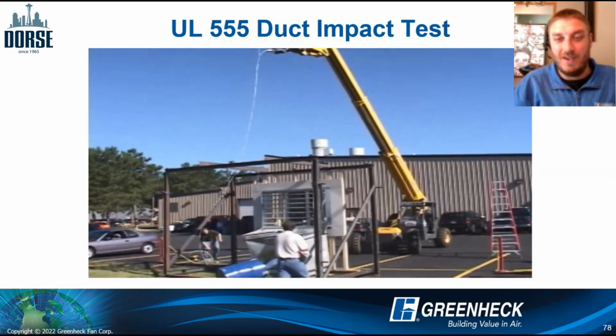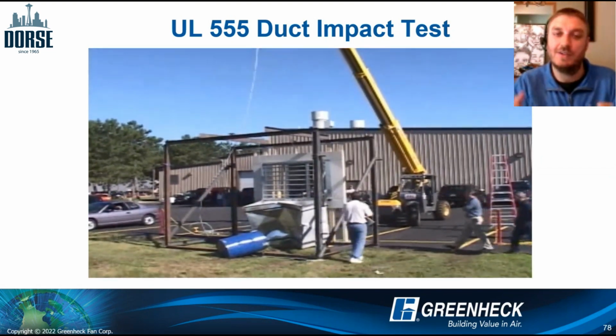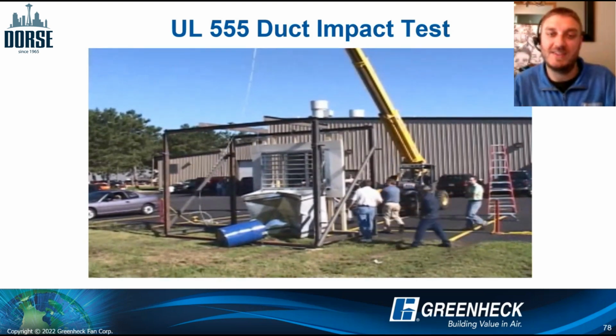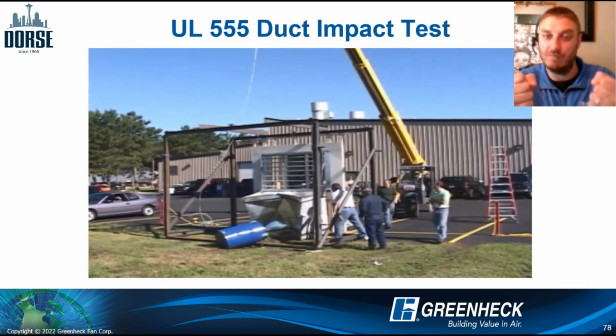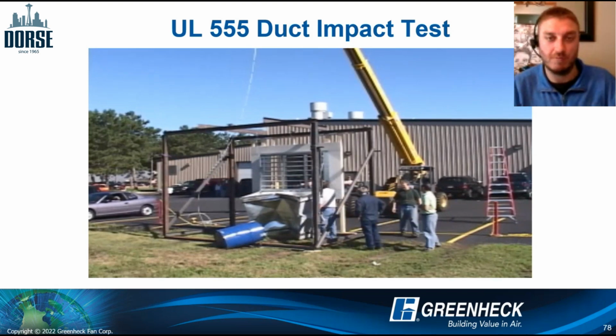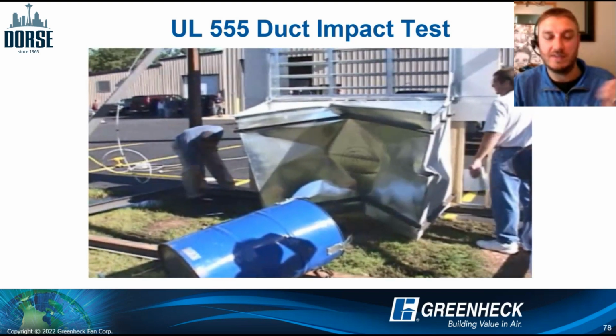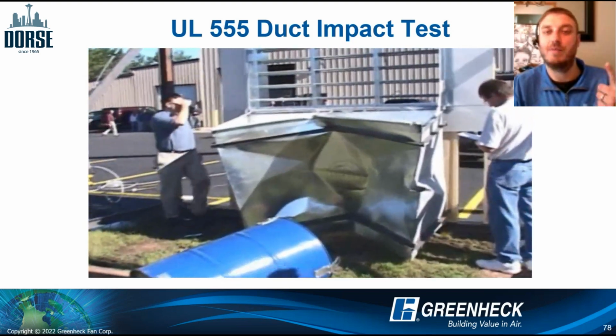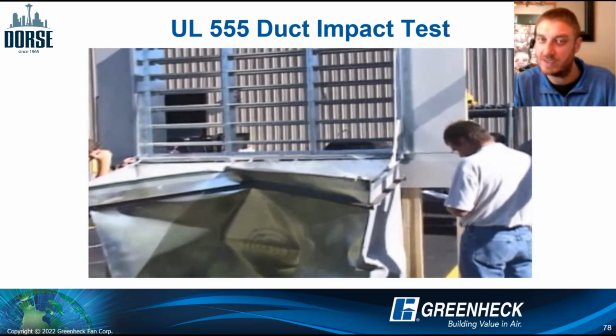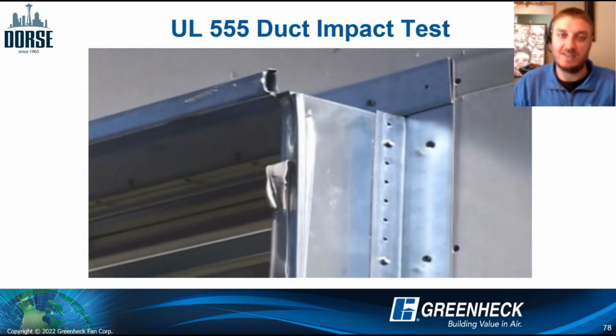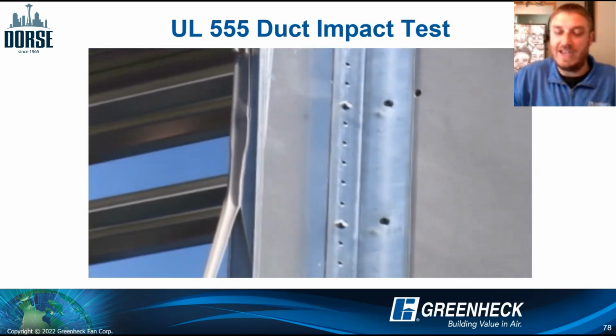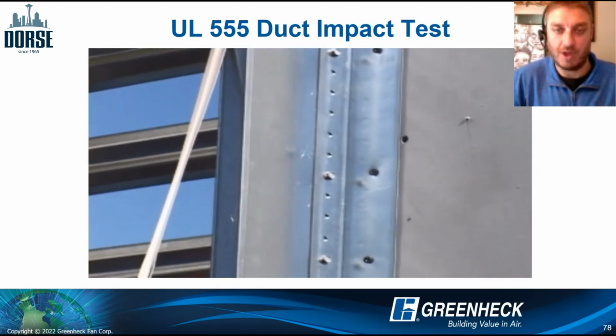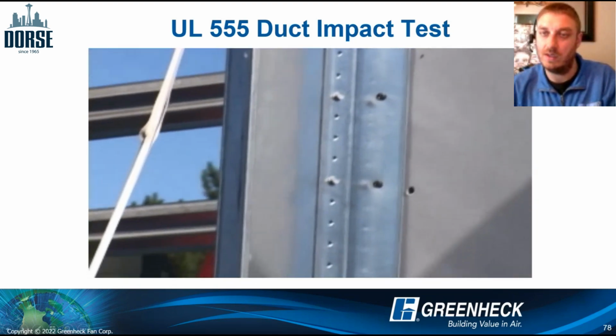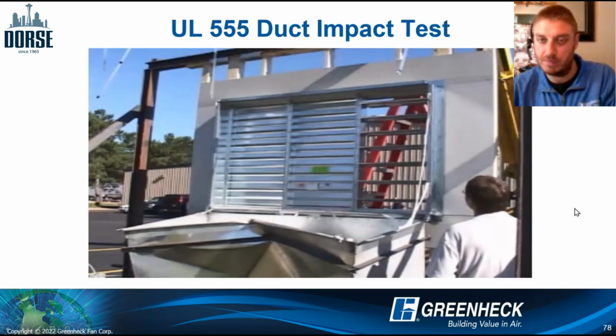But ultimately, again, we're testing to make sure that the installation method is sound, so the damper doesn't come ripping out of the wall, no screws come ripping out, the installation has not been compromised, and the operation of the damper has not been compromised. So that's the purpose of the test. Again, if you do have a catastrophic event, you want these products to remain and provide the purpose of their protection.